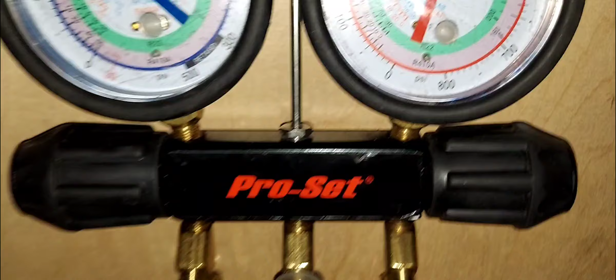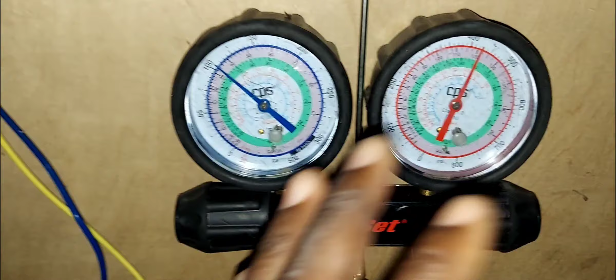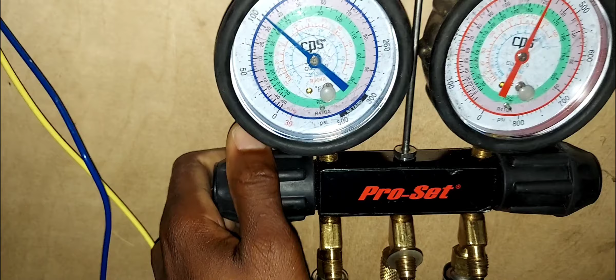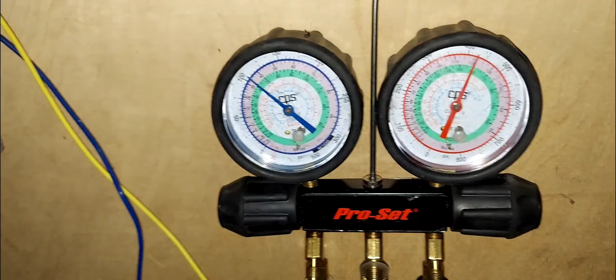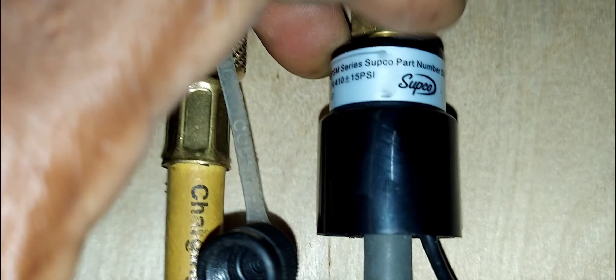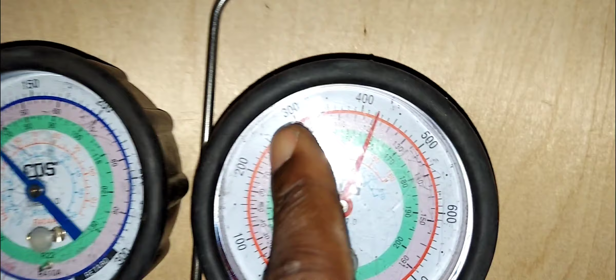We're tripped. Now, one thing I'm gonna tell you guys is that even though I don't recommend bypassing any safeties, my gauge is leaking. I don't know what's going on here. But anyways, you could take a chance if you want to take the chance. Let's just say this switch is bad and it's an emergency and you've got to give the customer cooling, bypass this one. That's fine. Bypass the low pressure switch. However, on the high side, if this is what you have right now, you see what you've got? 420 psi. The safety is tripped. It won't be able to reset right now. If you hit this button, nothing will happen, because the pressure needs to go down to a certain amount before it can be reset.